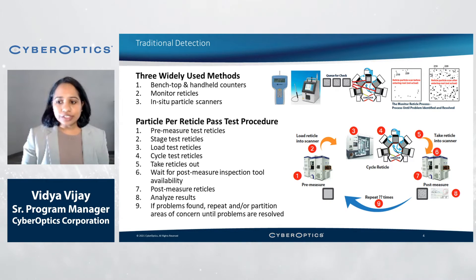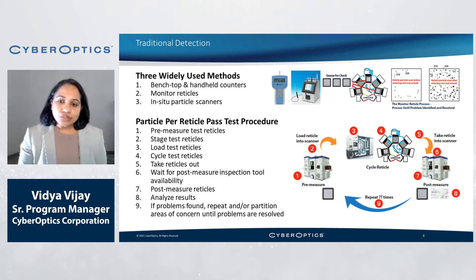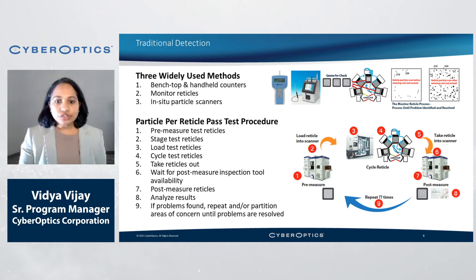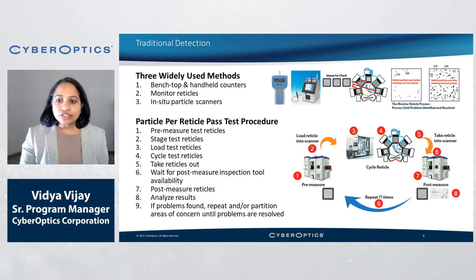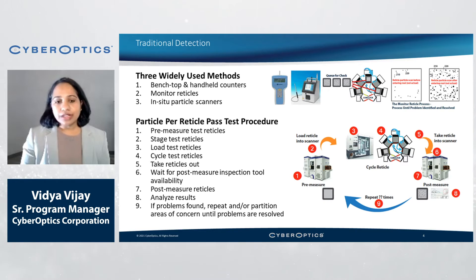Here is a flowchart of this process. Start with pre-measuring the test reticle, then load the reticle into the tool and cycle it as it would during normal operation. Take the reticles out and wait for post-measure tool availability. When the tool is available, post-measure reticles and analyze results. If problems are found, you repeat the same process all over again. This type of surface scanning method does not deliver results in real time, making it difficult to determine precisely when or where monitor wafers become contaminated.